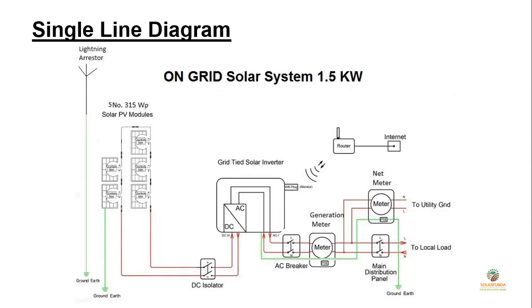Here is the single line diagram of my system, showing 5 numbers of 315-watt solar panels, followed by a DC-DB between the panels and a 1.5 kW grid-tie inverter, then an AC-DB after the inverter, a solar generation meter showing energy generated by the solar system, and finally the net meter. The AC connection also goes to the load through the main distribution panel. Earthing is shown by green lines to every component, there is a lightning arrester, and the inverter Wi-Fi is wirelessly connected to the home internet for remote monitoring of the solar system on a mobile phone or laptop.